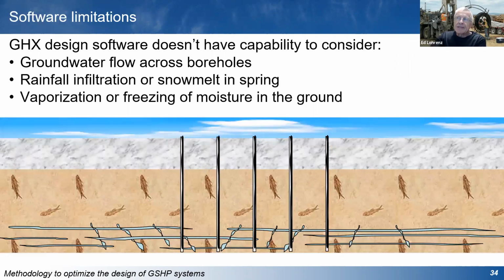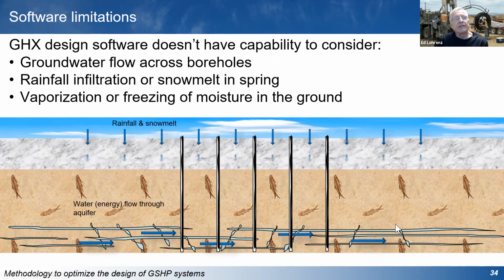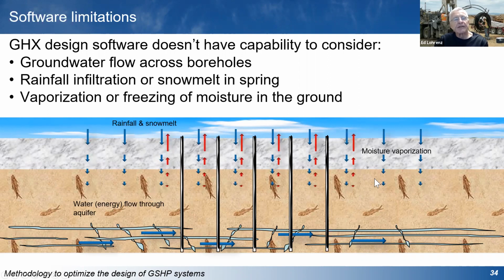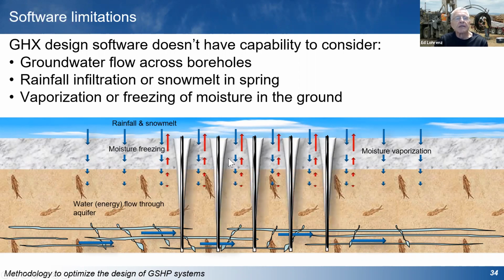Again, you've got to take into consideration that the software that's available these days, regardless of which software there is, doesn't take into consideration things like groundwater flow across the borehole field, which can take away excess heat and mitigate the increase or decrease in temperature over time. It doesn't take into account the rainfall and snowmelt infiltration into the ground, or the vaporization of moisture that might be in the ground in some conditions, or the freezing of the moisture in the soil around the boreholes. That's going to help stabilize the temperatures at just around the freezing point. So the software doesn't really tell you the full story. None of the software that's out there right now can take that into consideration. So that has to be a bit of a judgment call.